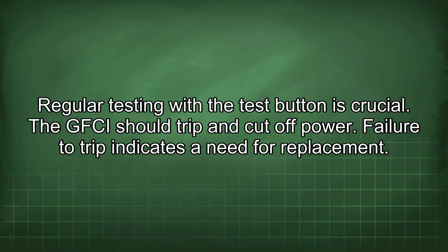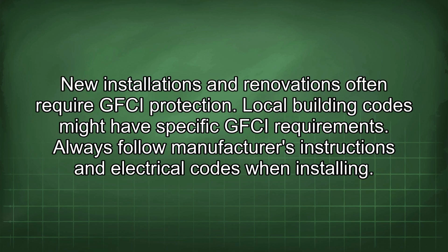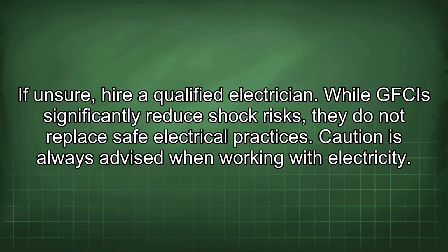Regular testing with the test button is crucial. The GFCI should trip and cut off power. Failure to trip indicates a need for replacement. New installations and renovations often require GFCI protection. Local building codes might have specific GFCI requirements. Always follow manufacturer's instructions and electrical codes when installing. If unsure, hire a qualified electrician.